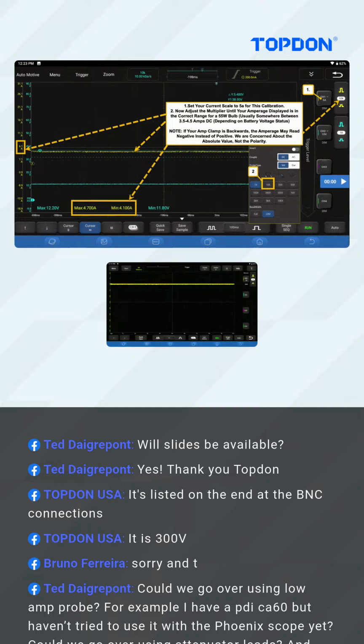Now, you asked another question about attenuators. Because the scope has an input range of 300 volts, you don't typically need to use one. However, if you want to use one, remember every attenuator has a rating or multiplier value that reduces the voltage coming into the scope by a certain factor or multiplier.